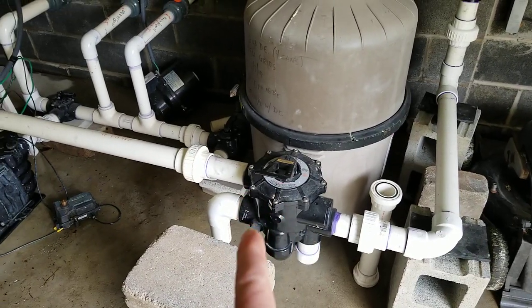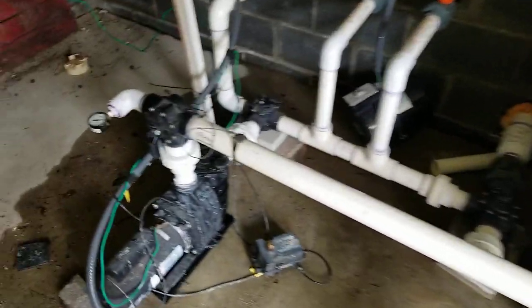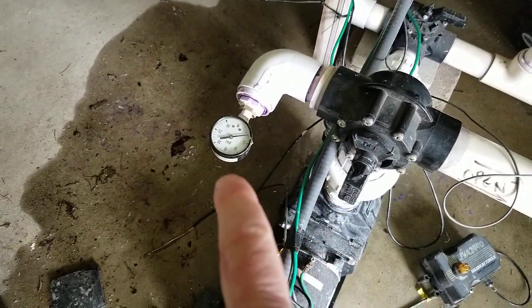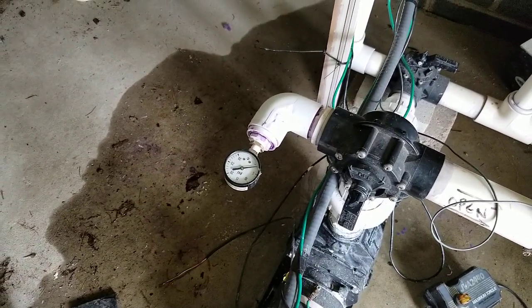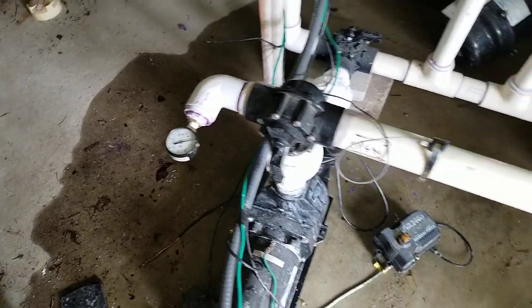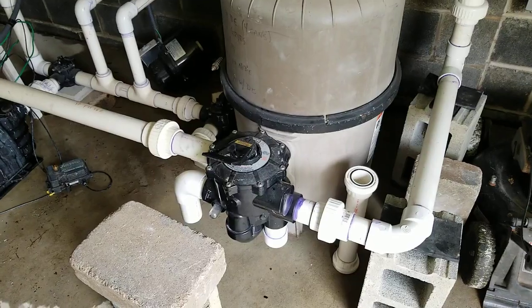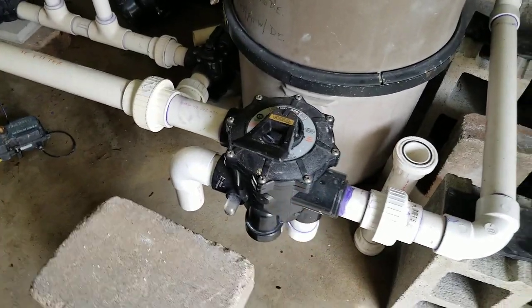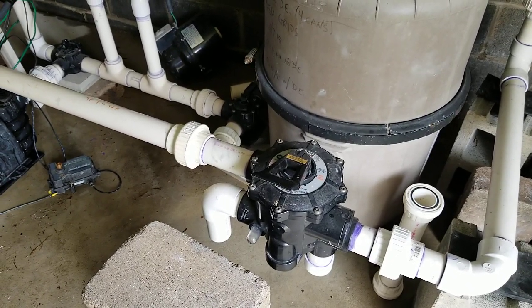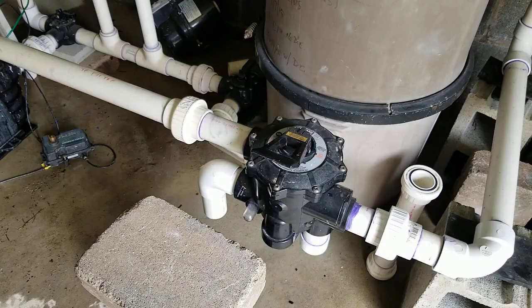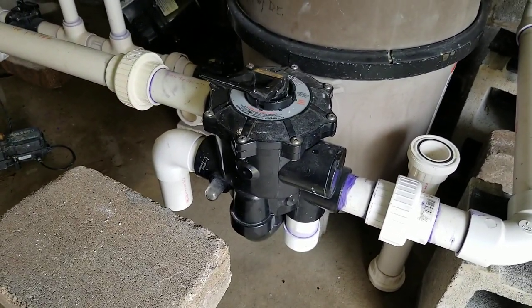So if we have delta P equals the sum of all our system losses, we're going to measure delta P. It's our outlet pressure minus 0 PSI gauge, atmospheric, at the outlet of our piping system. That's delta P on the left side of the equation. The right side is going to be all our major and minor losses plus our static head plus our diverter valve. The diverter valve is the one unknown in that equation. We will solve for how much pressure was lost across the diverter valve and back calculate what the equivalent L over D should be for that.